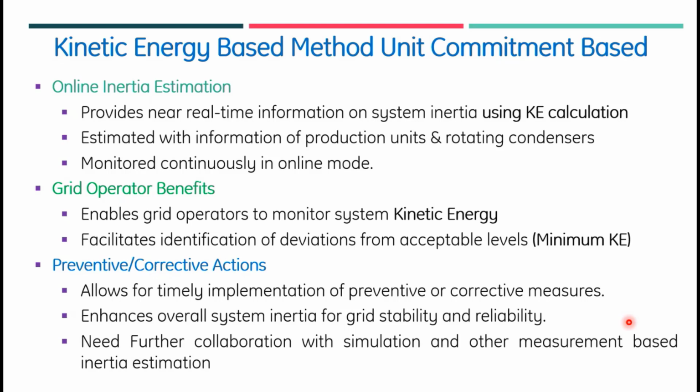Utilizing this, you can get, at this point in time, if this number of machines are in service, the synchronous kinetic energy of the entire power system, available from all the generators in the system. Okay, so that is for right now. Another thing is that you also know the day after tomorrow what your unit commitment strategy is, which units will be in service and which will not. Based on that, you can also forecast your kinetic energy.